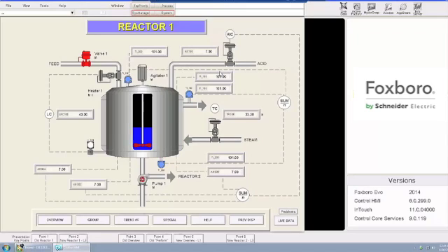The third problem is the way data is commonly presented, in this case, through a digital indication. Looking at this reactor, you can see that the temperature reading must be very important because there are three redundant probes, all measuring batch temperature. But looking at that temperature value right now, is this value good? Am I close to my set point? Am I within my optimal operating range? How about all three probes? I have to look around a bit to locate all three and mentally check the value. But without context, this is just data, and only an experienced operator could be sure of what he's looking for.